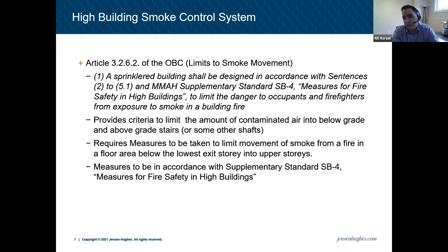So what are the articles saying basically? 3.2.6.2 of the OBC limits smoke movement. A sprinklered building shall be designed in accordance with Sentences 2 to 5.1 and MMAH Supplementary Standard SB-4, called Measures for Fire Safety in High Buildings, to limit danger to occupants and firefighters from exposure to smoke in a building fire. So basically, we're just trying to limit the movement of smoke to keep the occupants safe in certain areas that the building code is asking for.